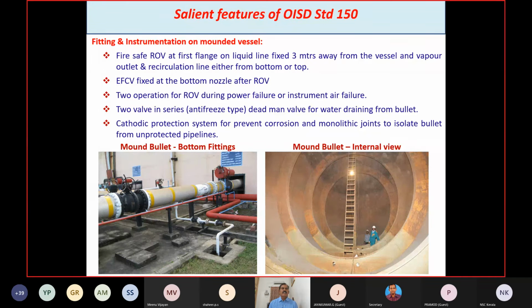And the cathodic protection system for prevention of corrosion, since the bullet is fully covered by earth material, so to avoid corrosion, a cathodic protection system is provided, and monolithic joints to isolate the bullet from unprotected pipelines. So the impressed current will be there, so we should not make contact with other pipelines. So monolithic joints are provided for all pipelines to isolate the bullet from unprotected pipelines.